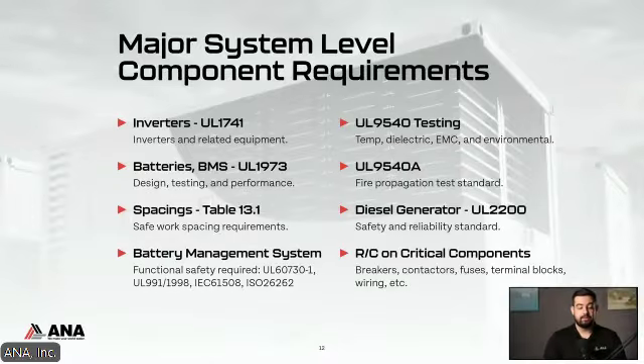9540 testing. So these are the basic electrical testing that you will have to evaluate to. These are typically across the board in most electrical standards. It's routine stuff like temp test, dielectric or high pot, EMC compatibility, and environmental tests especially for outdoor rated products. You could be susceptible to a rain test or impact or rigidity testing. This is enclosure testing to meet your outdoor requirements.